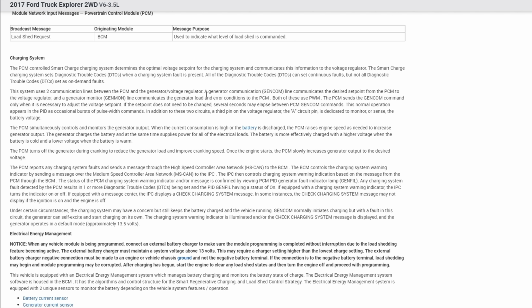The one known as the GenCom line, which is the one we're looking at, communicates the desired set point from the PCM to the voltage regulator. The GenMon line communicates the generator load and error conditions to the PCM. Notice both of these signal wires use pulse width modulated signals.